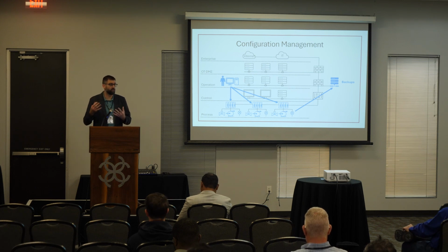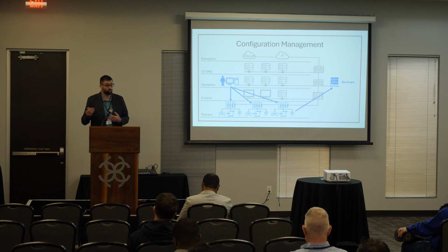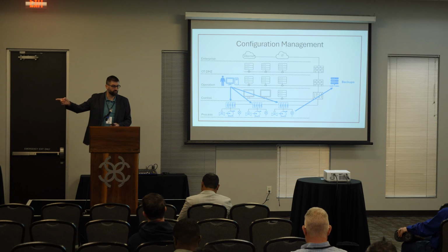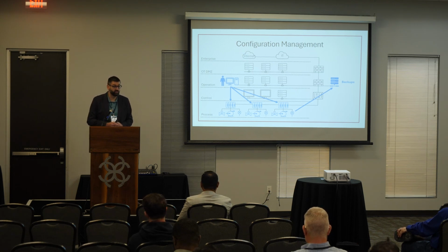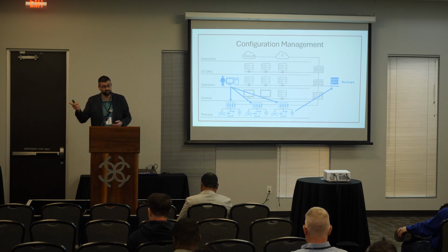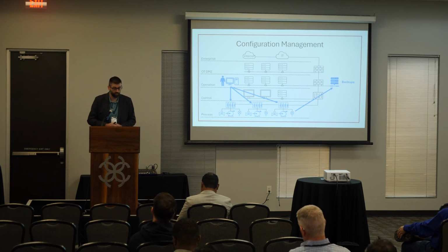Well, what about who's authorized to make those changes? We can set up alerts and rules that if so-and-so makes a change from this engineering workstation, I trust it. I don't need to know about it. But what about that PC on the other side of the county that has never made a PLC download, and all of a sudden it's making a PLC download? I might want to know who's making that change, why they're making that change, and I may want to go see who's sitting at that workstation.